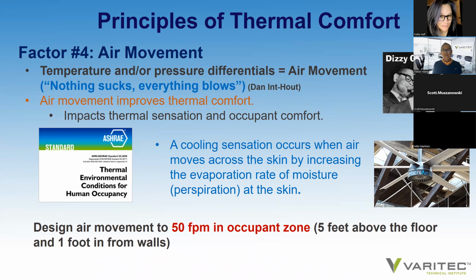If you have insufficient air movement in a space, you can reduce the evaporative cooling effect of an occupant and it may result in thermal comfort complaints. That's why ASHRAE designs air movement within the occupied zone of a building, defined as 5 feet above a floor and 1 foot from the walls, to be at 50 feet per minute. That is the hope, to create enough ventilation so our body air conditioning system works effectively by allowing the evaporation of perspiration to occur efficiently.